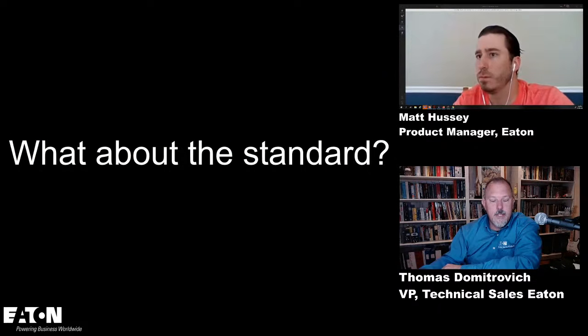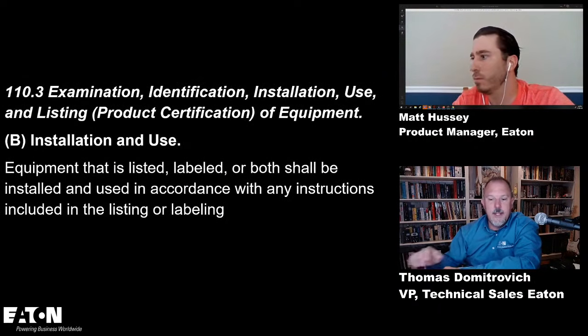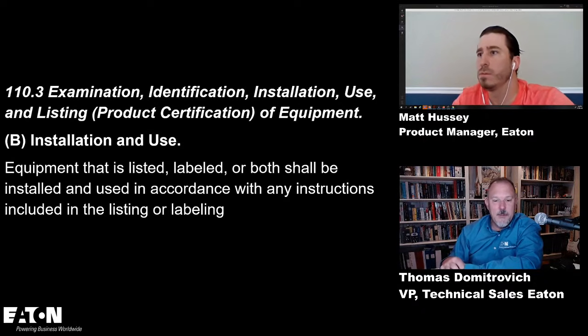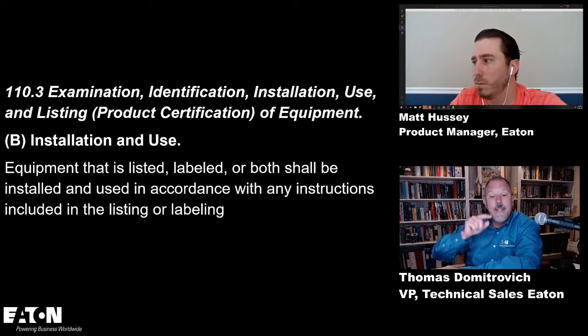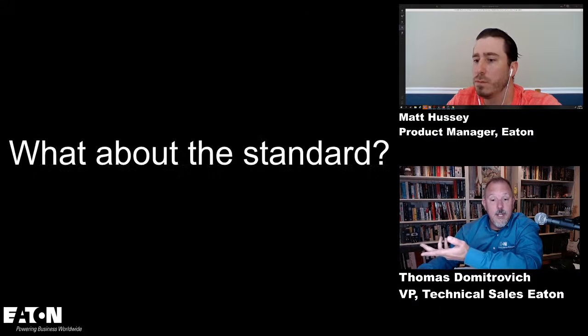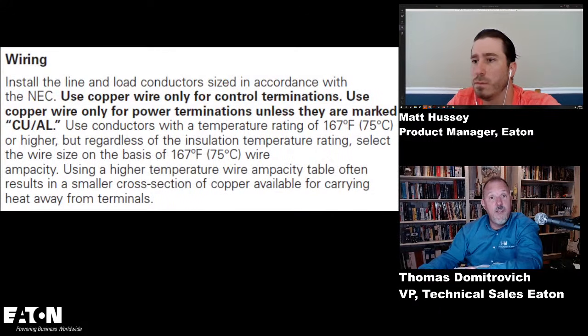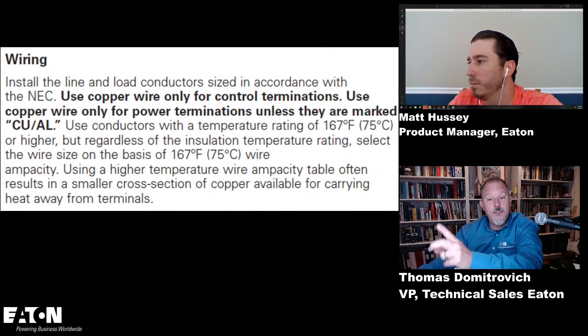Okay. What about the standard? I've got to look at the standard. I put that in for me and never went back to the standard, so I'm going to have to do that later probably. 110.3 talks about installation and use. So 110.3 tells us we need to follow the manufacturer's instructions, and what I just read to you is part of the manufacturer's instructions. So control wire is always going to be copper, at least in this assembly, and then you have to use copper wire unless it's marked CUAL.